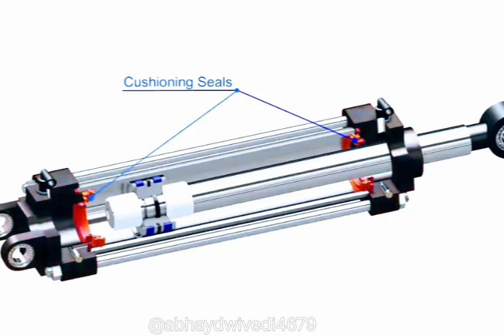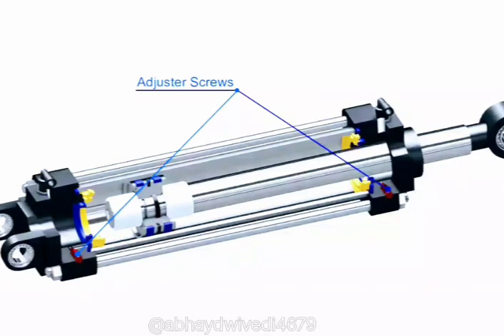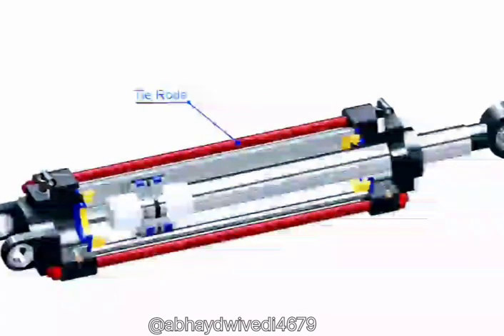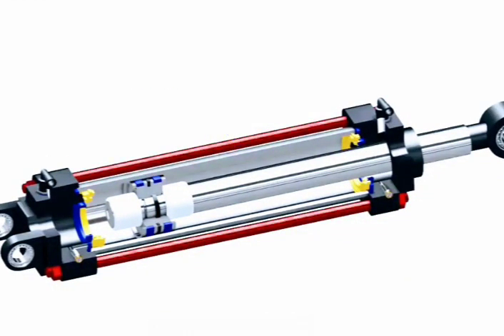Cushioning buffers and seals are installed on respective ends. Captive adjustable cushioning screws are installed on each end; these screws enable the user to adjust the optimum cushion at the end of the stroke. This whole assembly is held together with tie rods, which also provide compressive and tensile strength to the actuator.